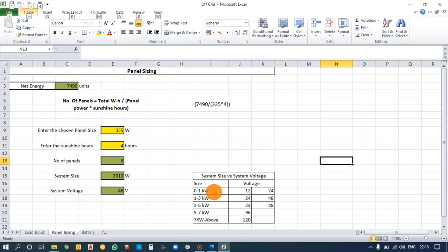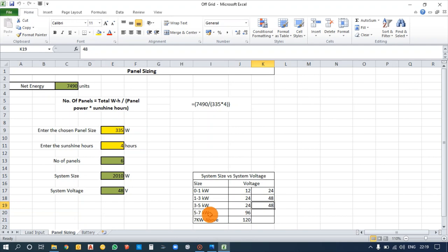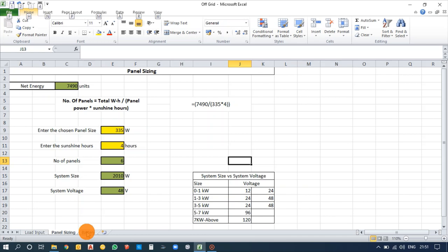In the market, a 1 kW inverter typically uses a 12V or 24V system; 1–3 kW inverters use 24V or 48V; and 3–5 kW inverters use 24V or 48V systems. You can select the voltage range based on convenience and battery availability. Above 7 kW, inverters use a 120-volt system. Now moving to battery design and calculation.